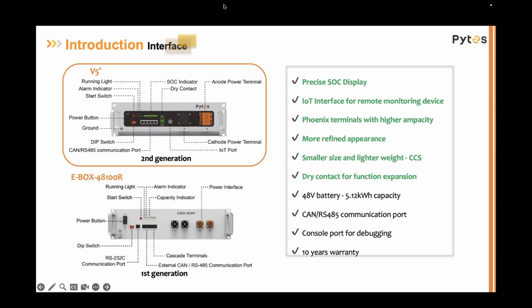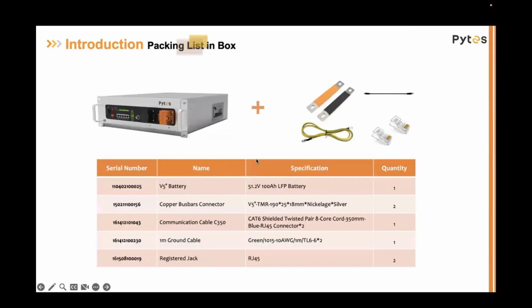On the next slide, this is what comes in with the battery when you order the V5. It comes with the bus bars I was just speaking about. These are 300 amp rated bus bars for the positive and negative anode and cathode of the battery system. It also comes with a grounding wire as well as a communications wire for us to daisy chain the closed loop communications within each of the battery systems in a stack.